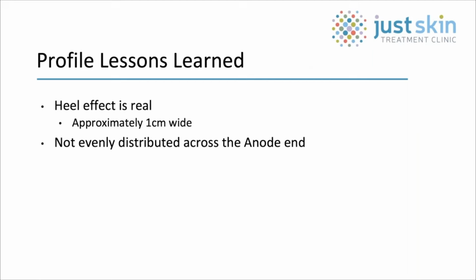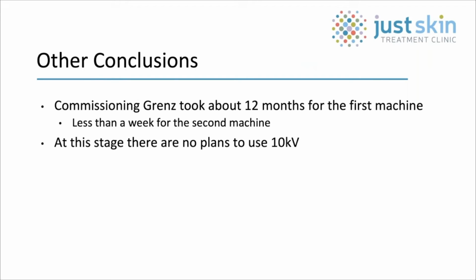When using smaller fields, like we have typically used to treat just skin, the heel effect is difficult to find. However, when using fields 15 centimeters and greater, it became evident. I should also add this data is only from one site, so it cannot be assumed to be present in all Grenz sites. Most of the practical issues within the department surrounding the use of Grenz have actually been issues with using the larger field sizes, as we have rarely used the 15 centimeter cones in the past.